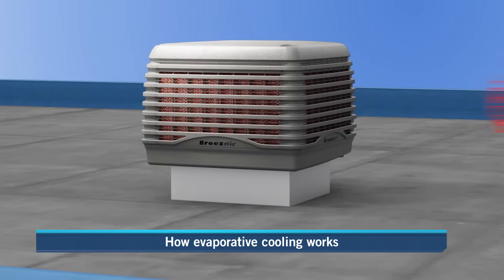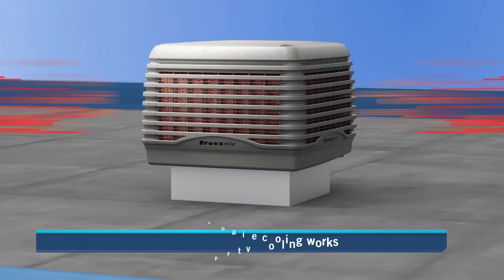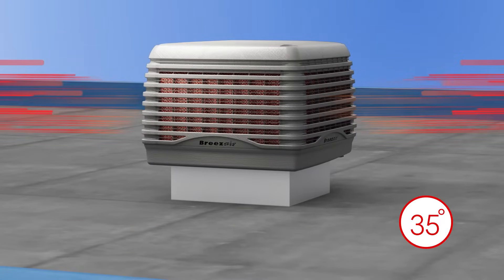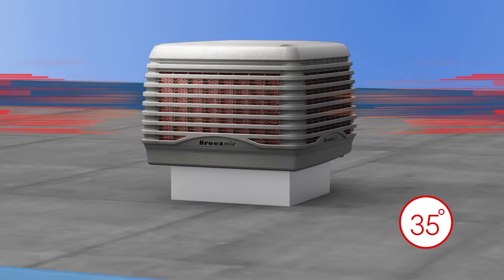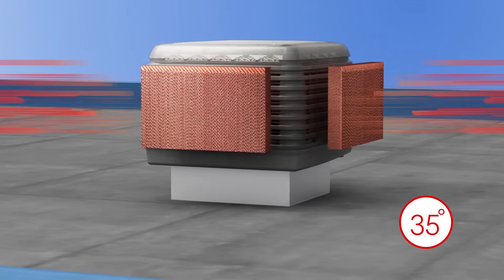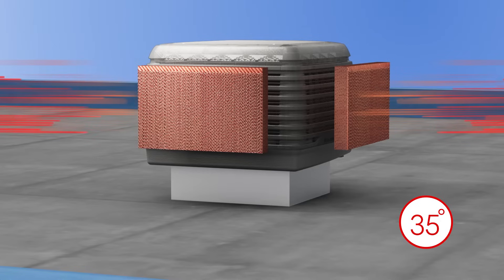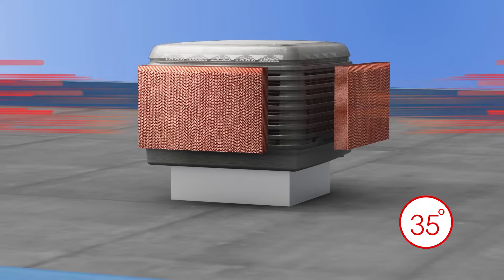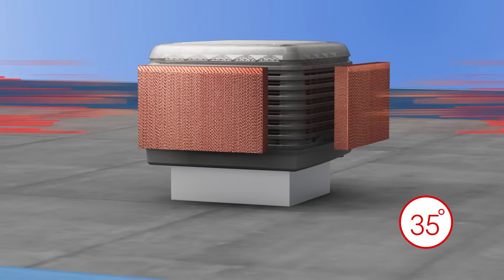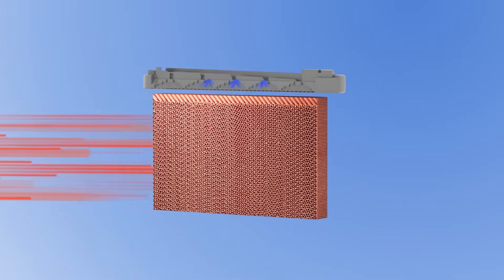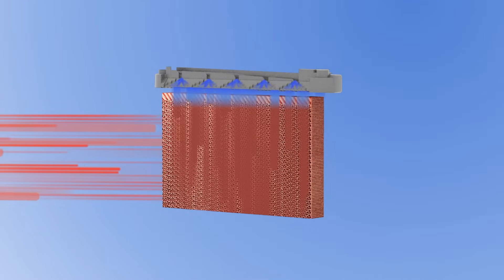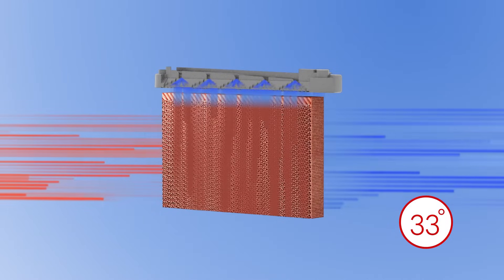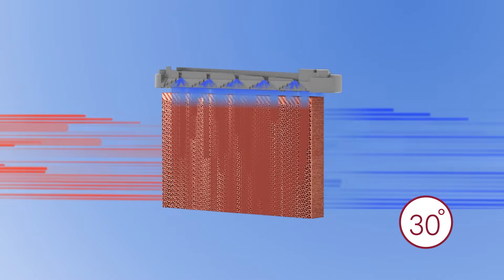As the name suggests, an evaporative air conditioner uses the principle of evaporation to cool air. The process begins when hot and dry outside ambient air is drawn through a series of water-saturated cooling pads. This hot incoming air stream provides the heat energy for evaporation. As it passes through the cooling pads, the water evaporates and the heat in the air is absorbed, which lowers the temperature of the air.